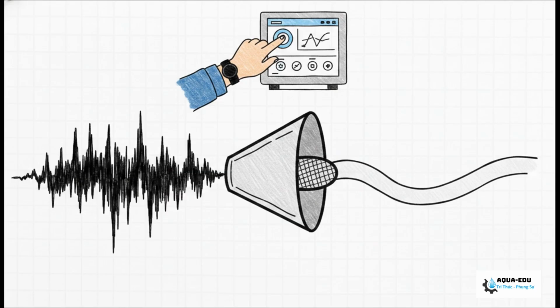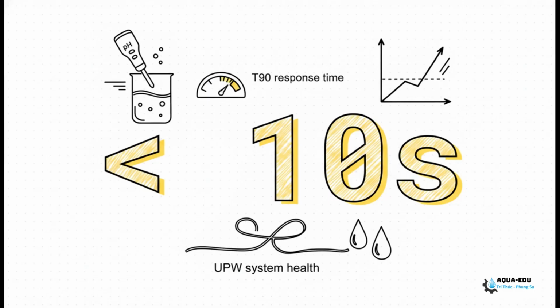It perfectly filters out minor water flow fluctuations and electrical noise, but it doesn't blind the system to real, actionable chemical changes. When you do your verification against a calibrated, portable, handheld meter, what you're really looking for is your T90 response time. The T90 is just the time it takes for the sensor to reflect 90% of a step change in pH. For a healthy, responsive UPW system, that time must be less than 10 seconds.